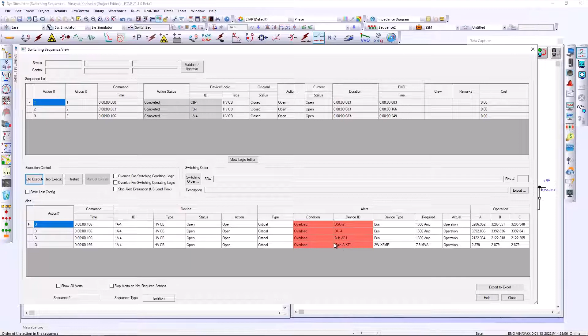As we run auto start on each step, we can observe the alerts are detected as I go through each one of the steps. Using the switching sequence manager, we can evaluate other potential issues, such as closing a ground switch without properly isolating the line.